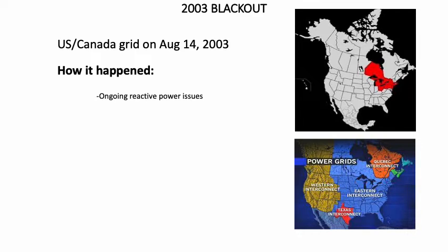There were reactive power issues noted leading up to the event. There were also software issues which led to the unavailability of the real-time system information. They used this real-time system information to help troubleshoot in real time to isolate sections of the grid, which could be helpful when trying to prevent cascading events from occurring. So without that, cascading events are likely.